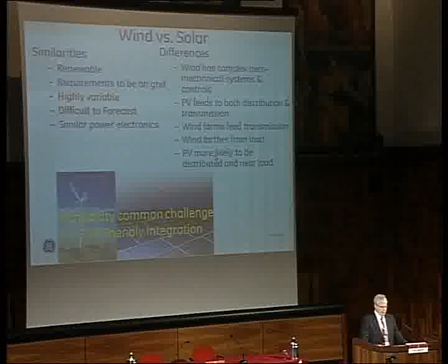In some cases, they want power sources tying into the grid to have so-called frequency droop characteristics, so it's self-regulatory. If the frequency is going up, that means there's too much power going in, and you want the system to be able to relax back. There are also ramp rate constraints that are used in dispatch to do the control.